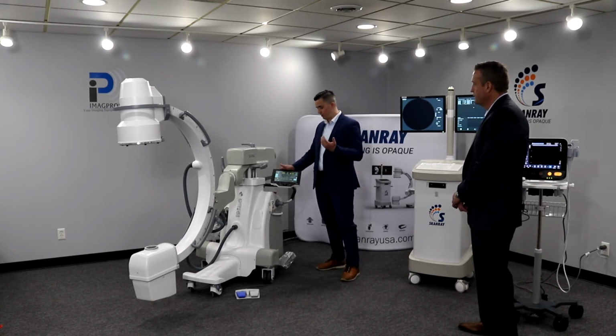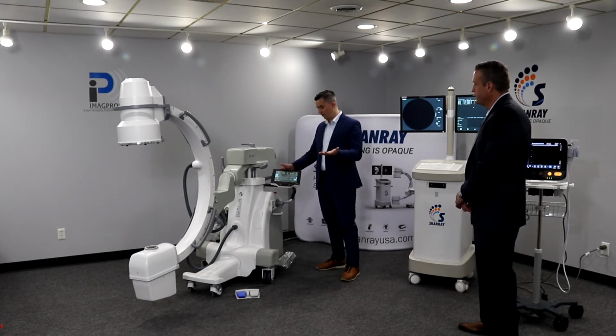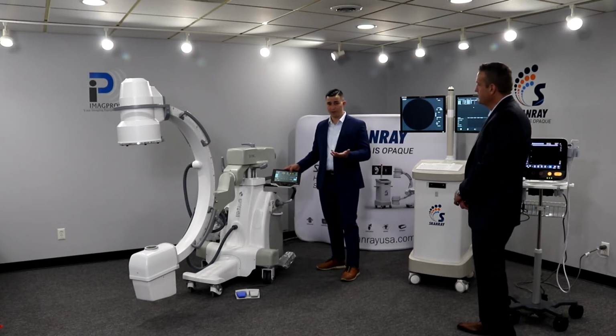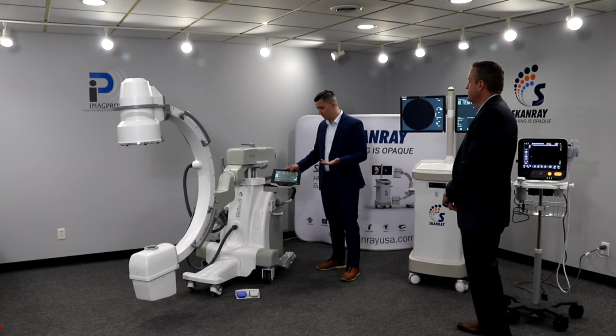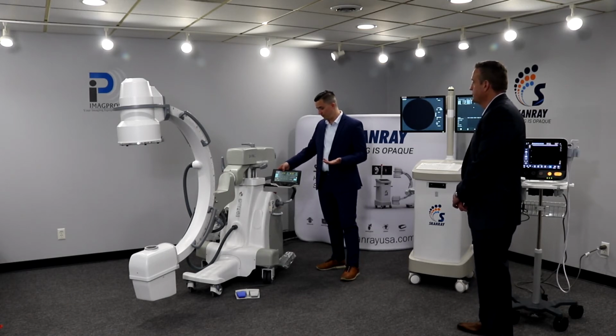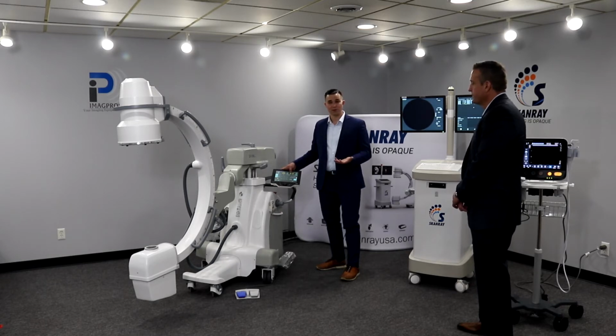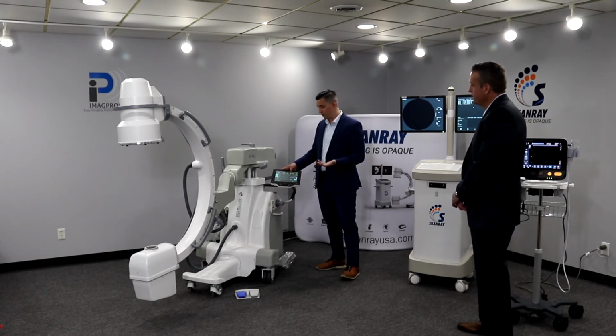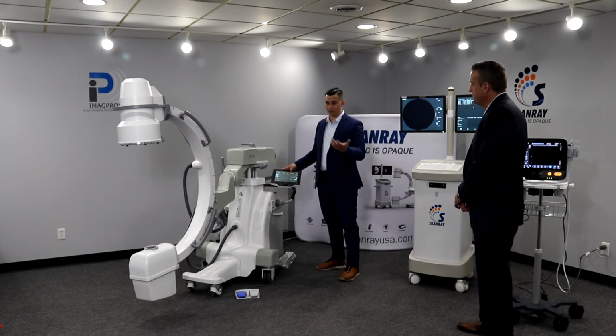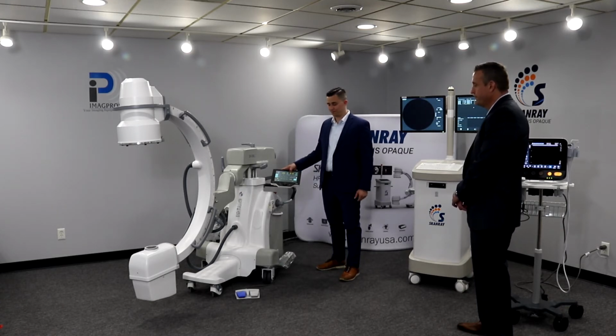So whereas if we would take a picture of my hand right now, it would show up at 45 kV and maybe 0.1, 0.2 mA. On a competitor system, you might see around 55 kV and maybe 1.2 mA. So it's almost a fifth reduction in dose delivered to the patient, and that also in turn makes less scatter as well. Yep, very good.